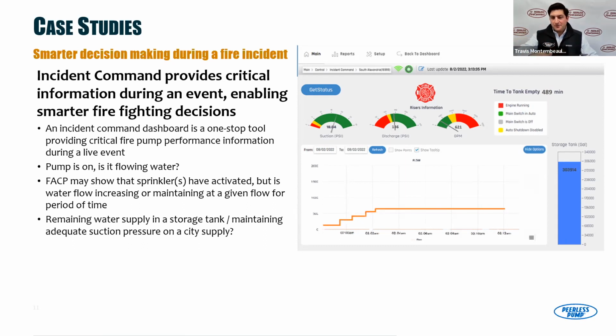And if you're looking over time, so this chart shows you here, time on the x-axis and flow on the y-axis. It begins to look like stair steps over time. So sprinkler head opens, flow jumps up, then over time it's flat because you've only got the one head open. All of a sudden another head opens up. So flow jumps again and again and again. But what happens once that fire is contained? You're no longer opening sprinkler heads, but the pump's still on. You're still flowing water, but over time that flow rate is constant. So you see that plateau here, that long plateau on this chart. That's indicative of hopefully a fire that's under control.